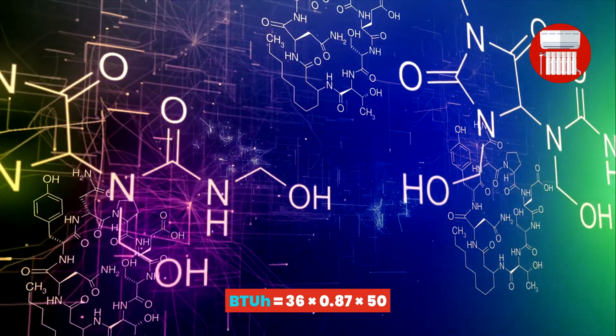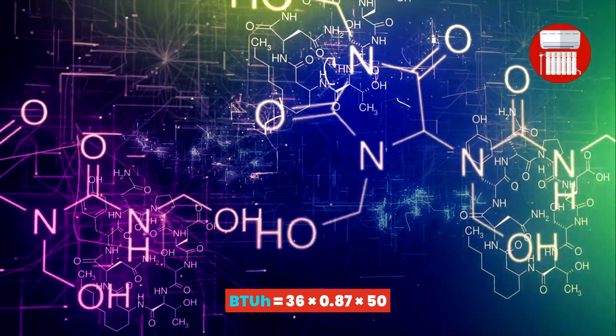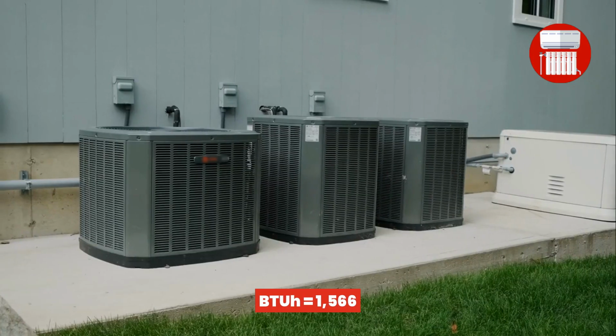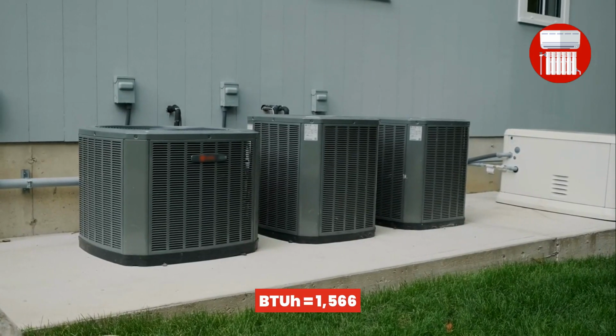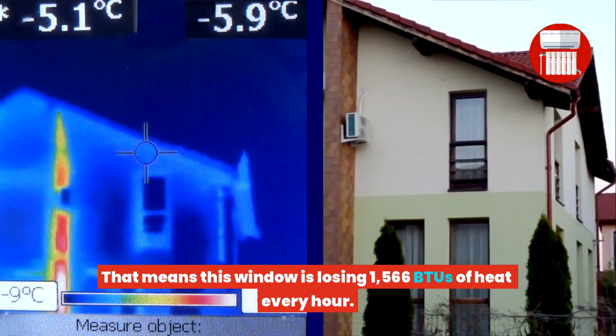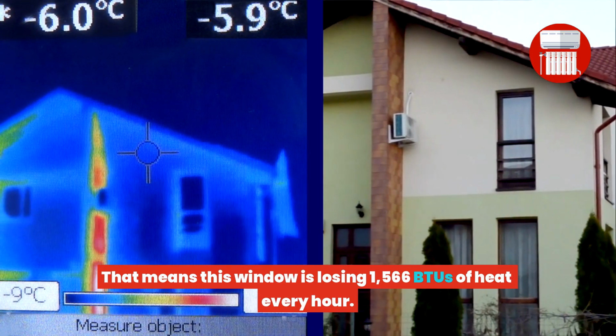Now plug in the numbers. BTU = 36 × 0.87 × 50, so BTU = 1,566. That means this window is losing 1,566 BTUs of heat every hour.